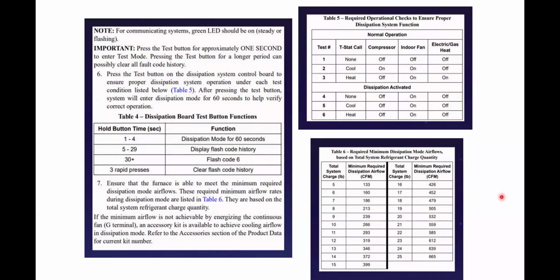All the fans, whether it's a furnace, a fan coil, air handler, rooftop unit, the fan speed has to be set up. The minimum fan speed has to be set up so it has at least the minimum of these charts, enough to dissipate the problem. So if we go back to our 11-pounder refrigerant example, we need at least 293 CFM whenever the fan is enabled by the thermostat.